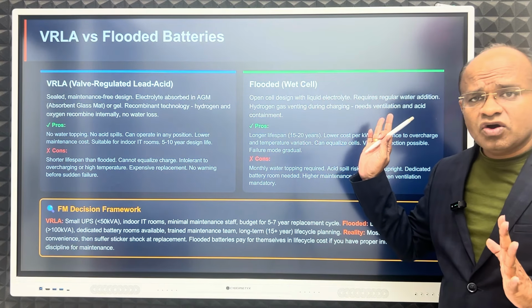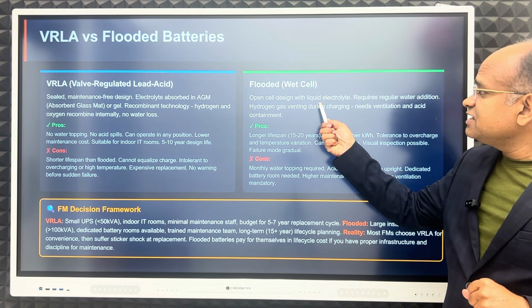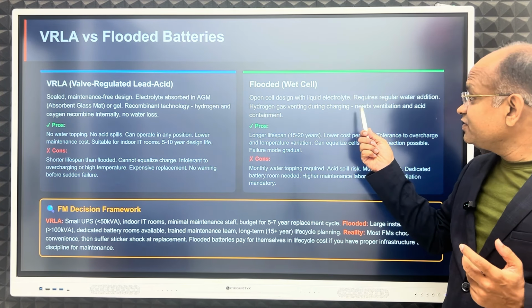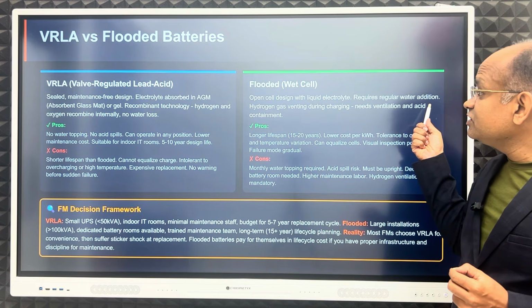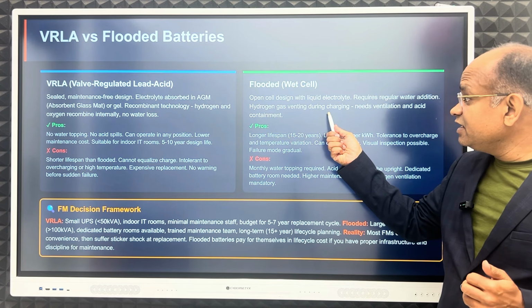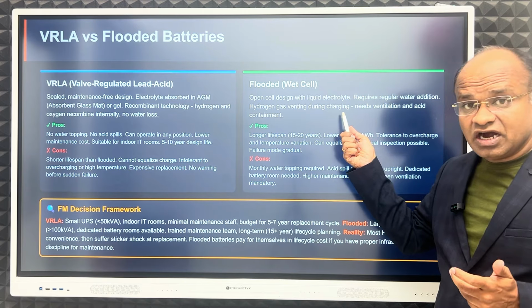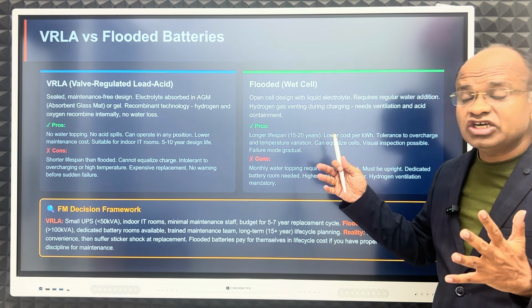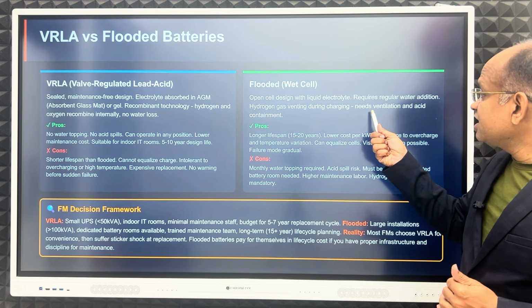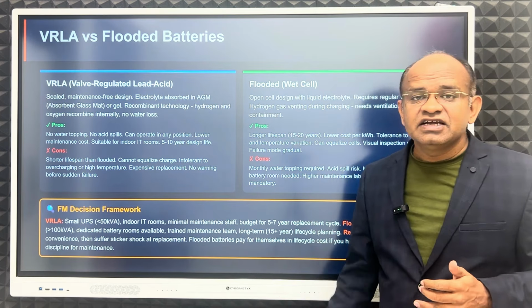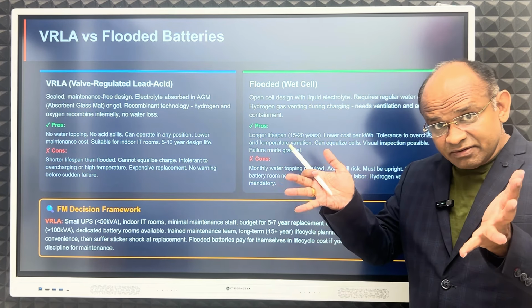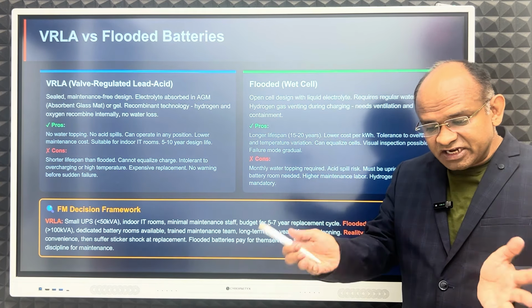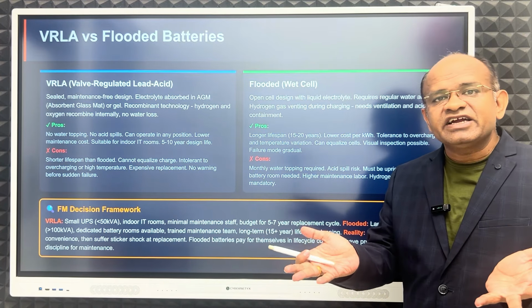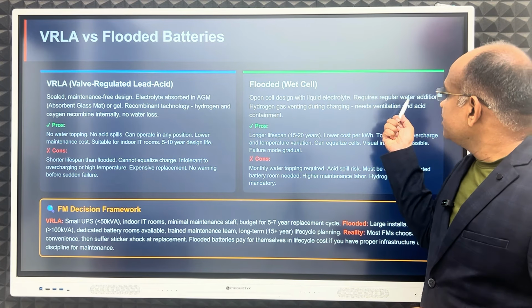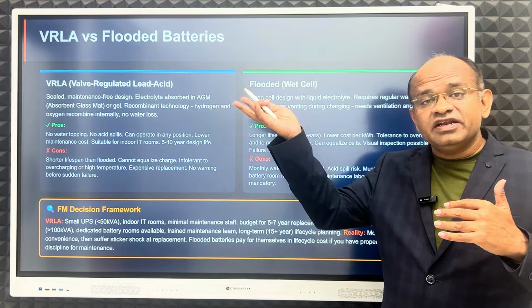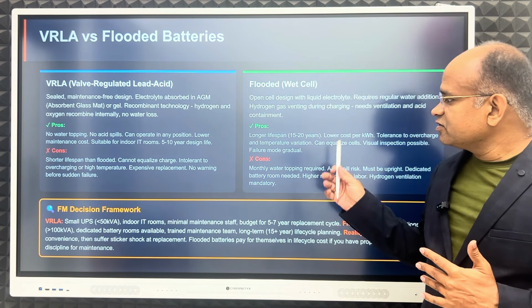Flooded or wet cell is an open cell design with liquid electrolyte, requiring regular water addition, and hydrogen gas venting during charging - hydrogen gas comes out while charging, which is dangerous. These old batteries need ventilation and acid containment, otherwise acid spillage below should have containment, and ventilation for the hydrogen gas emitting through that.